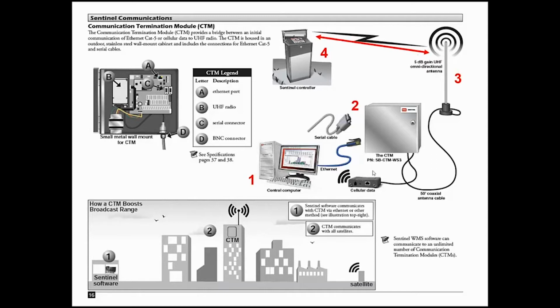But also what you have to understand as well is that when you transmit radio signal to a controller, and you see the example is a stainless pedestal right there. Those stainless pedestals come with what we refer to as a pancake antenna. It's a flat omnidirectional antenna that's secured to the lid. Now, that's only 3 feet up off the ground. If all of a sudden landscapers come in and plant shrubs around the pedestal to hide it, or they build a new parking garage, whatever, things can change.